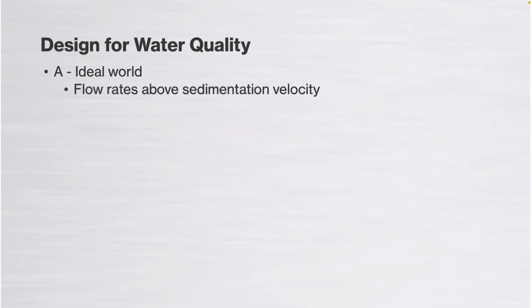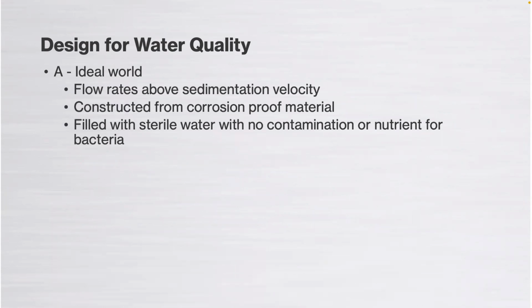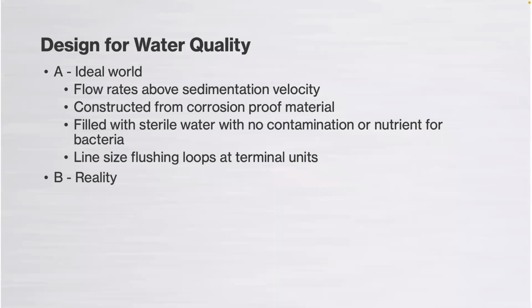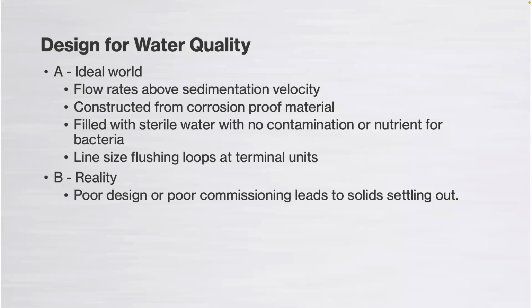in an ideal world, we'll have flow rates above sedimentation velocity, constructed from corrosion-proof material, and of course filled with sterile water with no contamination or nutrients for bacteria. There'll be line-size flushing loops at terminal units everywhere. But the reality is we sometimes have poor design. I'm not suggesting anyone online is going to design a system poorly, but in reality, sometimes there are poorly designed systems or they're poorly commissioned.